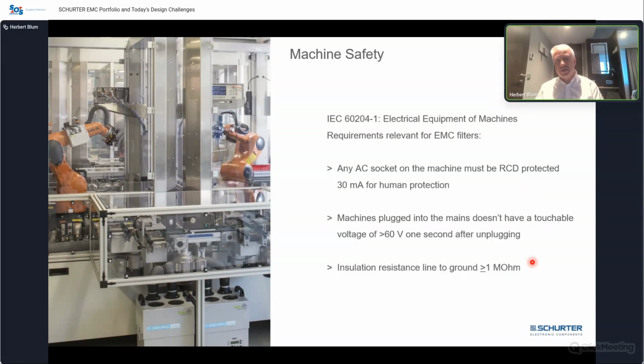Now, what's required according to the machine safety standard? First of all, if you have an AC socket, it must be RCD protected. And the typical value for RCD protection is 30 milliamps. So whenever a ground current above about 30 milliamps occurs, this RCD will trip off. This is basically human protection. Then another topic is, whatever machine is plugged in and you have a connector that you can pull out, after 1 second you should not have any touchable voltage on the connector pins of more than 60 volt.